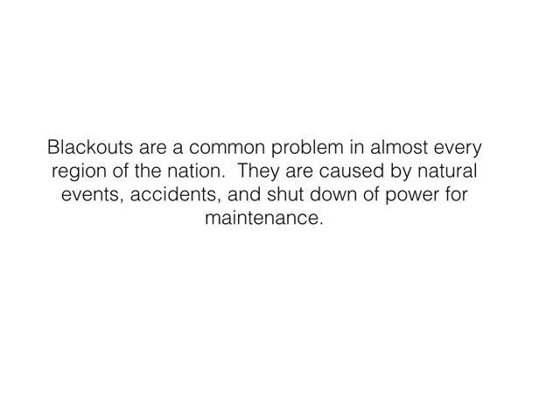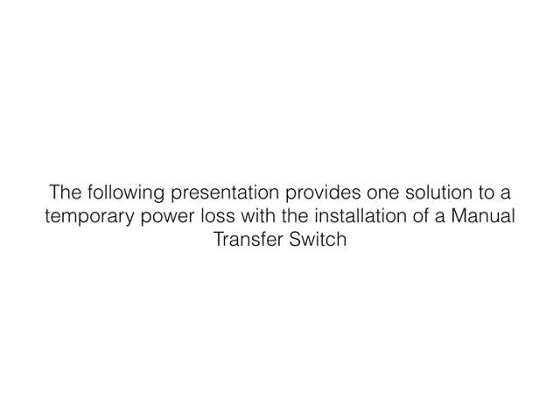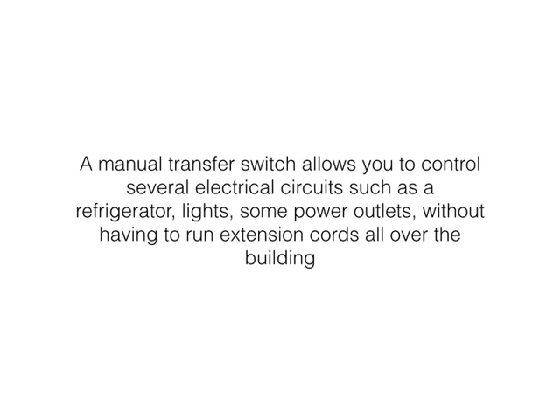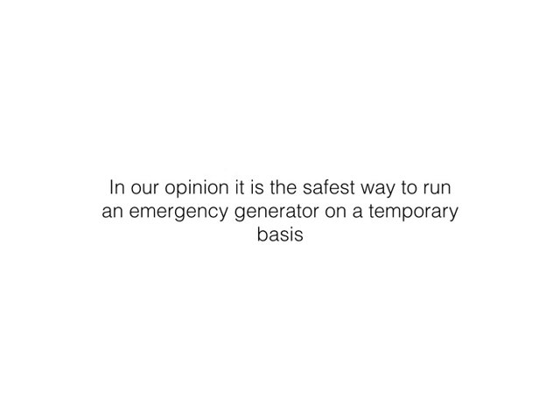Blackouts are a common problem in almost every region of the nation. They are caused by natural events, accidents, and shutdowns for maintenance. This presentation provides one solution to temporary power loss: installing a manual transfer switch that works with a standby generator. A manual transfer switch allows you to control several selected electrical circuits without running electrical cords all over the building. In our opinion, it is the safest way to run an emergency generator on a temporary basis.